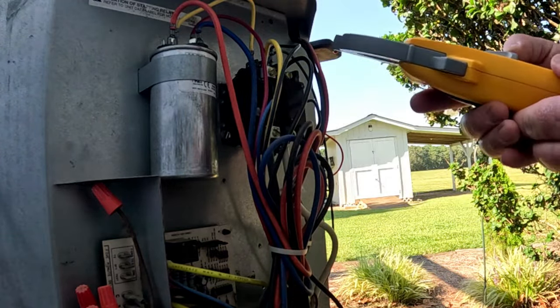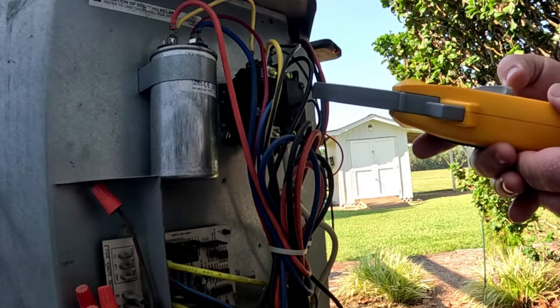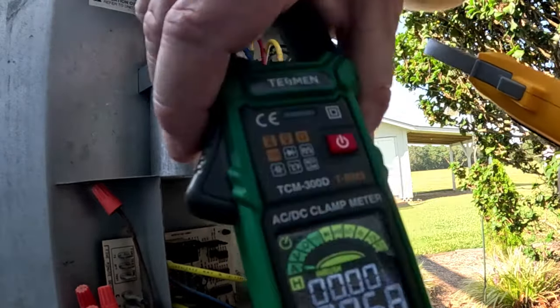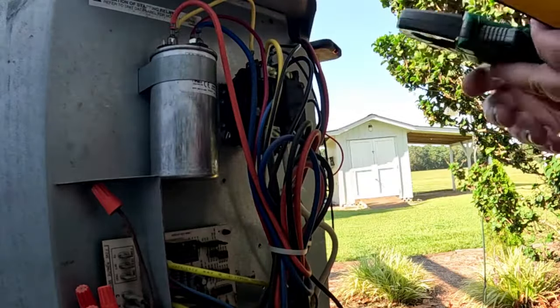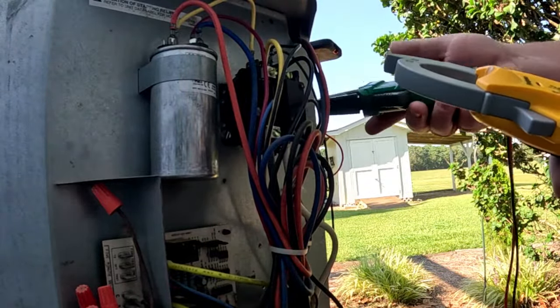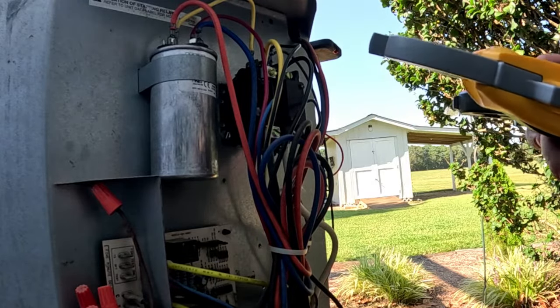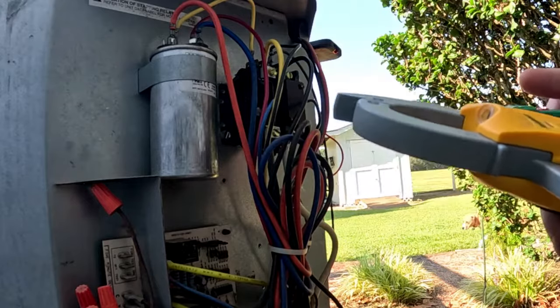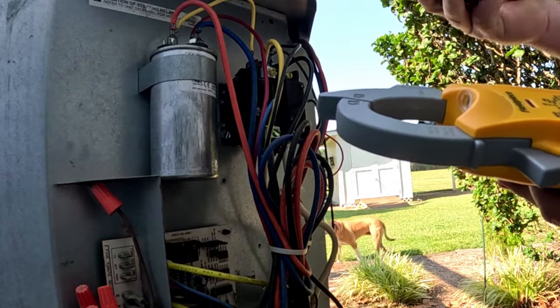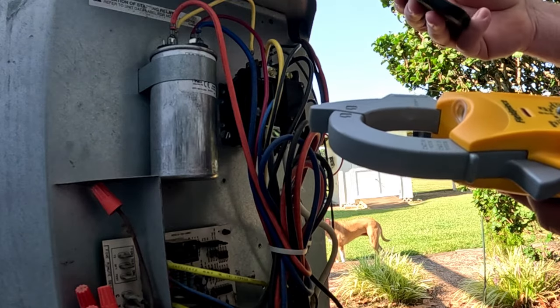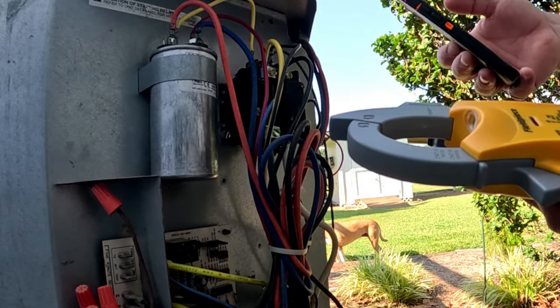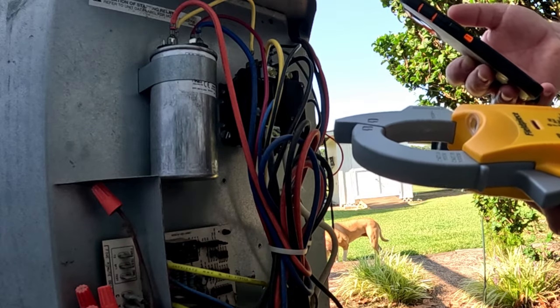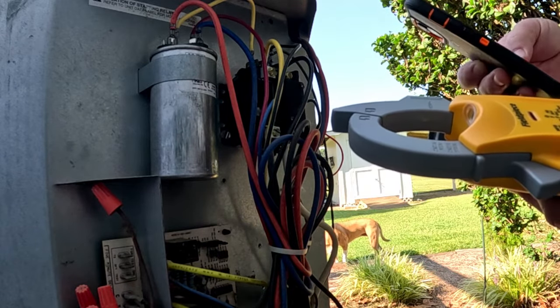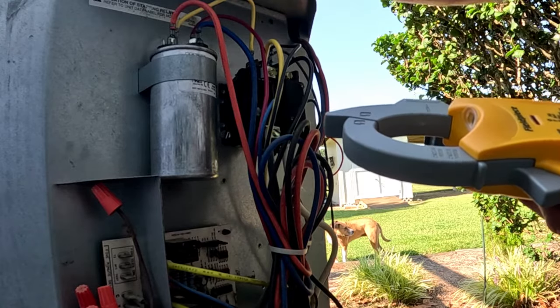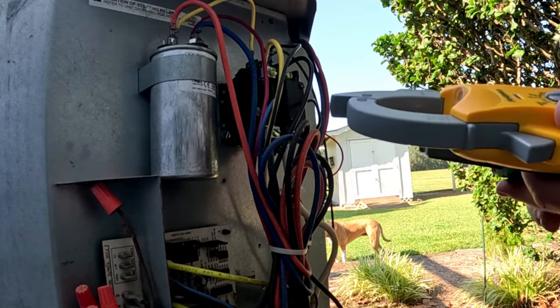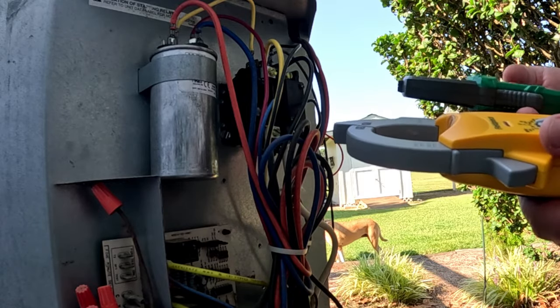So let's check our operating amp comparison. We had 85 on this, 88 on the FieldPiece. I put a new capacitor in this not long ago. But this unit's 15 years old, so the compressor may be getting close. Maybe it's getting time for me to start looking ahead at replacing my unit. I can tell you it won't be one of them damn XVs though. I can promise you that.